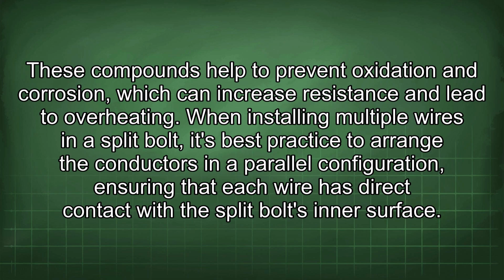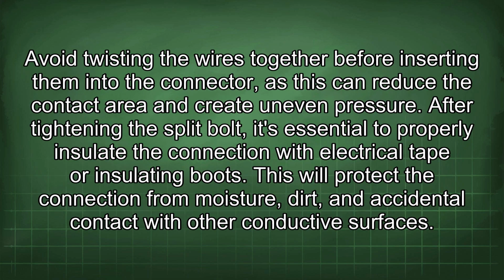When installing multiple wires in a split bolt, it's best practice to arrange the conductors in a parallel configuration, ensuring that each wire has direct contact with the split bolt's inner surface. Avoid twisting the wires together before inserting them into the connector, as this can reduce the contact area and create uneven pressure. After tightening the split bolt, it's essential to properly insulate the connection with electrical tape or insulating boots. This will protect the connection from moisture, dirt, and accidental contact with other conductive surfaces.